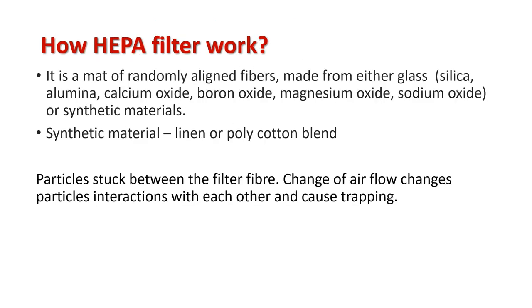The HEPA filter works as a mat of randomly aligned fibers made from either glass or synthetic material. Glass materials can include silica, alumina, calcium oxide, boron oxide, magnesium oxide, and sodium oxide. Synthetic material can be linen or poly-cotton. Particles get stuck between these filter fibers, and changes in airflow change particle interactions with each other, causing trapping.